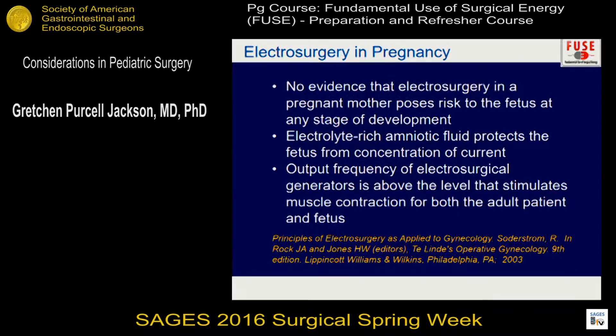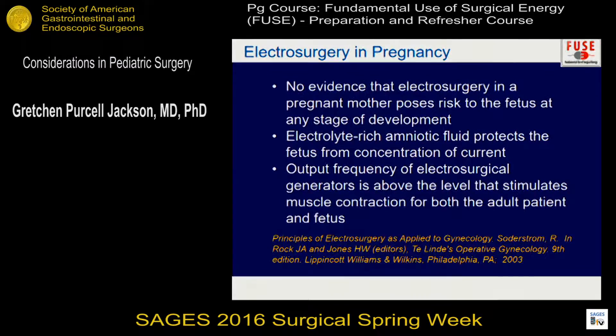Our youngest and smallest patients are the fetus. There is no evidence that using electrosurgery in a pregnant woman poses any risk to the fetus at any stage of development, unless you are at a site performing fetal surgery where an active electrode could directly contact the fetus. The fetus is protected by electrolyte-rich amniotic fluid. Additionally, the output frequency of electrosurgical generators is at a level that does not stimulate muscle contraction, either in the adult patient or in the developing baby.